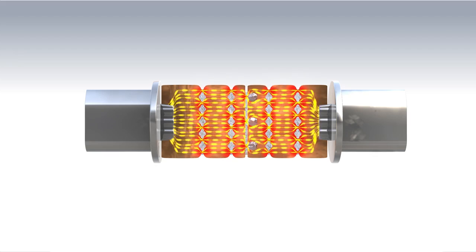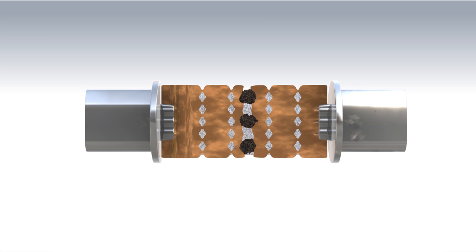This leads to a weakening on the narrow point near the soldering point until the fuse element is interrupted at this position. This process normally takes several minutes or even hours depending on the current flow.